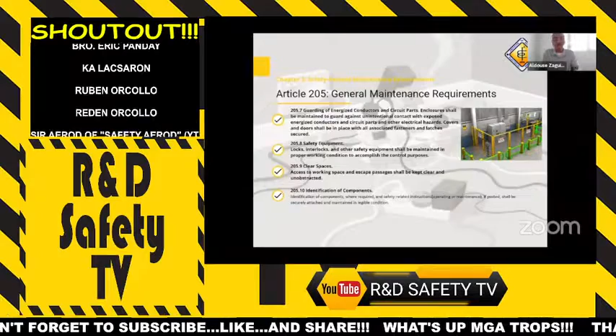Identification of the circuits. And let me add here, bago pa makalimutan, arc flash. Again, the PEC1, dati, tubra na sa atin yung mga signs like this. But now, PEC requires that that equipment be tagged - switchgear, motor - be tagged on the arc flash hazard. So there should be a hazard showing the incident energy, the category, the required PPE, the identification of the equipment, and who to contact if there are questions or clarifications needed on that particular equipment.